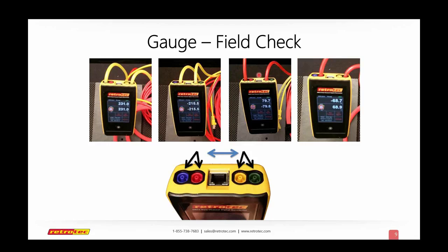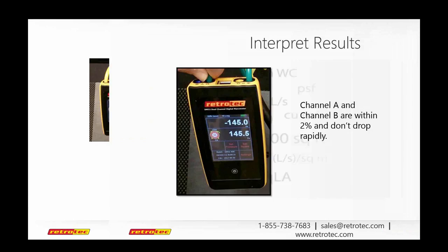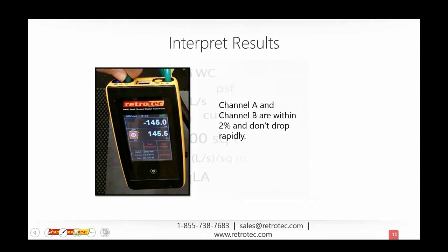Any questions about that? So let me finish this next slide. So again, the idea is that both channel A and channel B should be within about 2%. That shows you that your gauge is working. And if you get any sort of rapid drops in pressure, that usually means that the pressure that you built in the tube when you plugged it onto the ports is being released, and that usually means that there's something wrong with the tube.